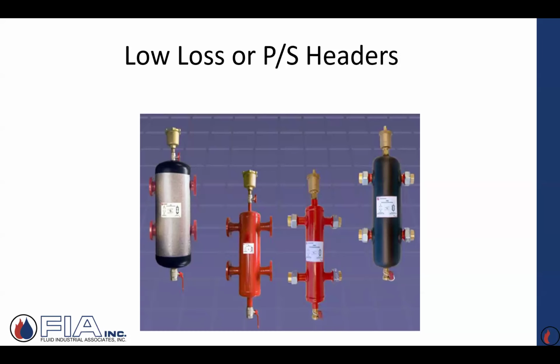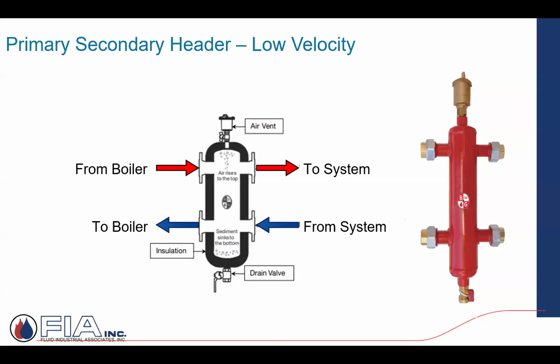The last device that's made its way onto that commercial setting is referred to as either a low loss header or a primary secondary header. We'll see this again in week 3 when we talk a little bit about primary secondary pumping and piping. But this device kind of performs a few different functions. It starts off being called a primary secondary header, or a PSH. And what they're saying here is this is such a low velocity device that I can hydraulically separate, say, my boiler plant from my distribution system. And because of that low velocity, I can act like an air separator as well. And so they'll do that.